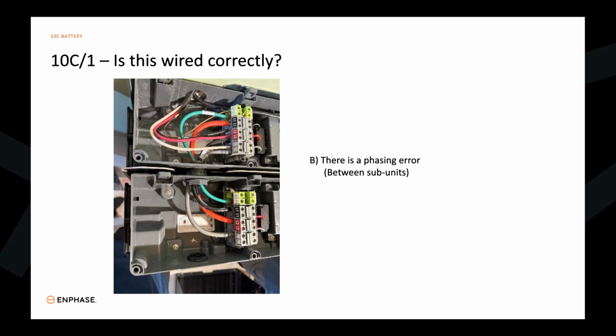I actually witnessed this, I knew the installer that did this. Total honest mistake. I talked to him about it, and he totally owned it. It took us about an hour because we found it during the commissioning part, but we were able to fix it, remedy it, and close out the site and commission it. To his point, he's so used to landing line 2 to 2, 1 to 1, that he didn't pay attention, even knowing there's a phase swap on the wires that he needed to do. He just blanked that out from years of being an electrician and wiring that way. This is very specific how we must phase swap our subunits within our 10C.